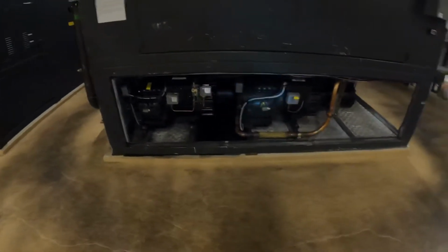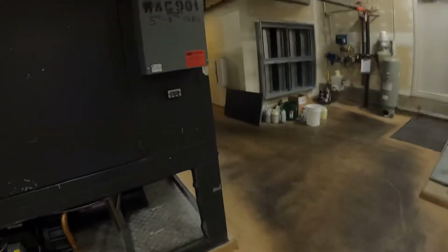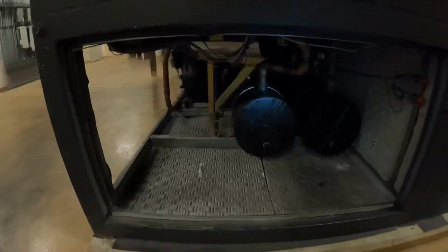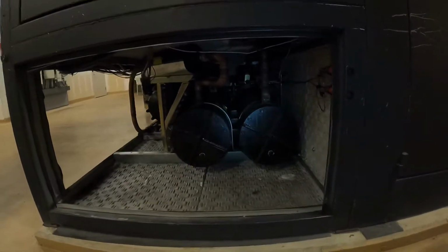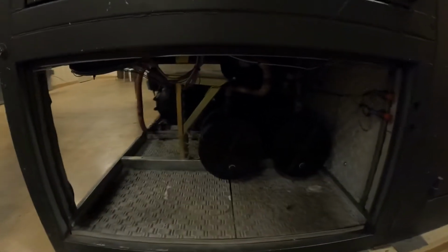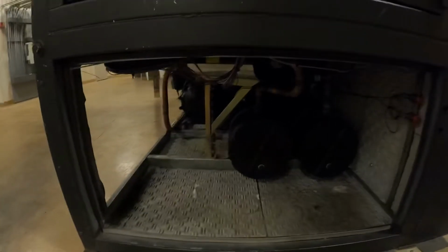Now we need that heat to go someplace. So we're going to end up running our heat gathering refrigerant through our compressors, coming off as a hot gas into a couple of condenser barrels. Now these condenser barrels have the hot gas refrigerant coming in one side of it, coming out liquid refrigerant the other side, because we took the heat off of it via water. So those refrigerant passes that go back and forth through that barrel are covered by water. That water's taking the heat off.